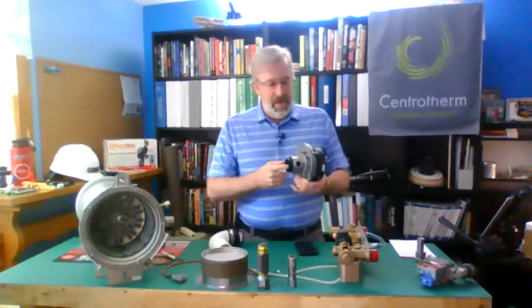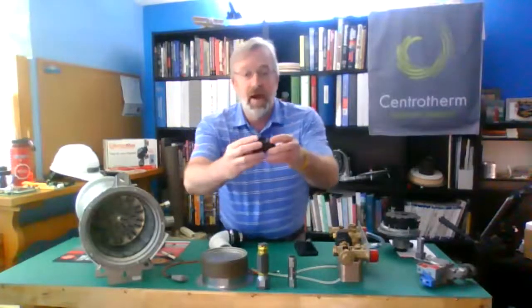So when the fan runs, this is my incoming air, which comes in through the air intake pipe into the venturi. If I take the venturi apart, I've got to make sure I lean toward the right camera. What that shows me is I have an orifice here and I have an orifice there.